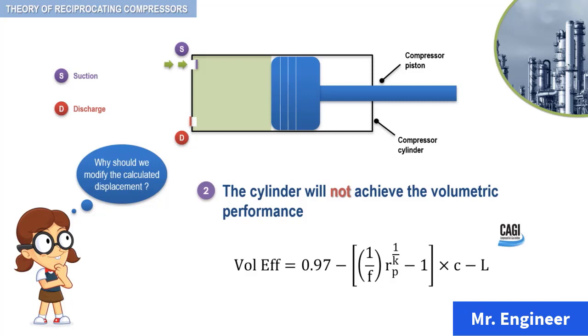The term L that you can see here is added at the end to allow for gas slippage past the piston rings in the various types of construction. If, in the course of making an estimate, a specific value is desired, you can use 0.03 for lubricated compressors and 0.07 for non-lubricated machines.